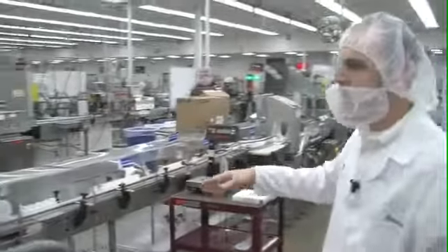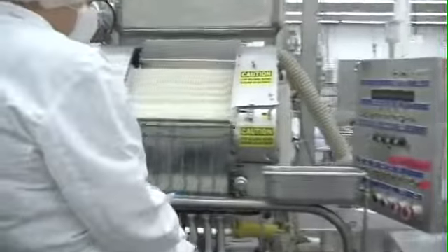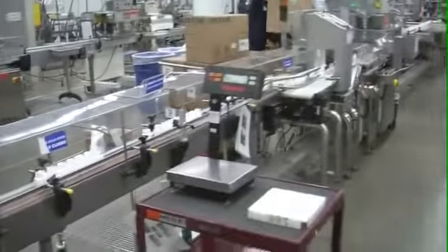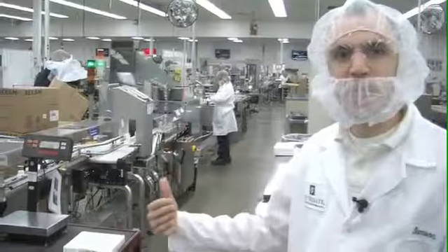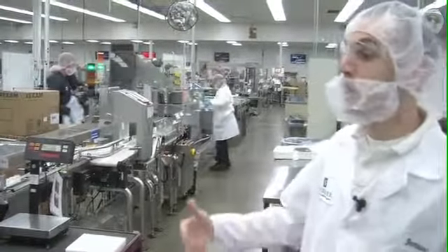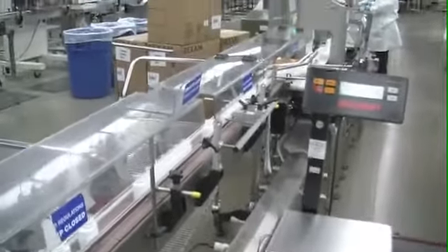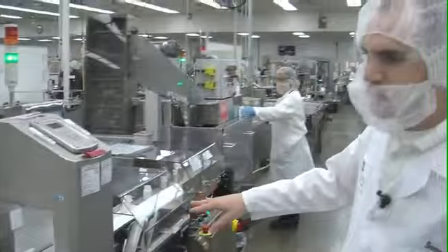After you go through that, the conveyor belt is going to go through a check weigher. This check weigher is going to see if a bottle is too light or too heavy. Too light means that they don't have enough tablets. Too heavy means that they have too many tablets. The conveyor belt will just shoot those bottles off the line so that there is a consistency with all the tablet numbers.